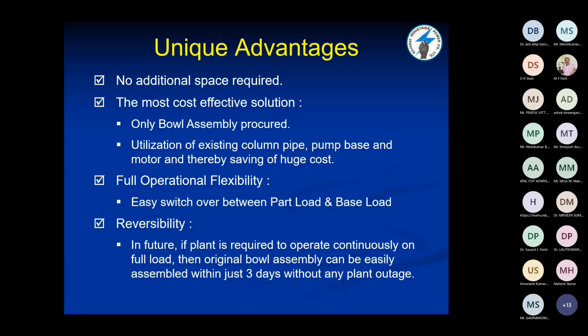Now these are the unique advantages of that project. No additional space was required because we fitted the pump at the same position. Only the bowl assembly was procured. The existing column pipe, pump base and motor were utilized, thereby saving huge cost, because all the pumps, column pipes and motor are the same. And there is full operational flexibility because we retrofitted only one pump. The other 2 pumps already have higher capacity. So when the plant is running at full load, we can operate the full load pumps. And when the plant is operating at part load, we can use this retrofitted pump. So we can easily switch over between part load and base load operation.